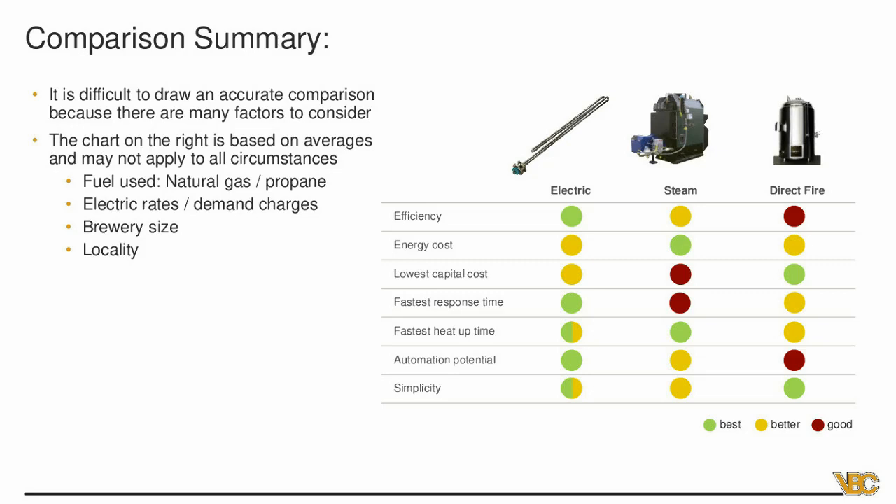Automation potential: electric is very easy to automate. We use PWM — pulse width modulation — to run those elements anywhere from zero to 100%. You can turn them on and off remotely. Steam is a close second — it depends on how it's set up. If done with manual valves, there's not much automation. When we do control systems for steam, we put in motorized globe valves to vary from zero to 100%. Direct fire — the majority of systems I see use on/off control for the burner, though modulating burners exist for direct fire where you can send an analog 0-10V signal to vary the flame.